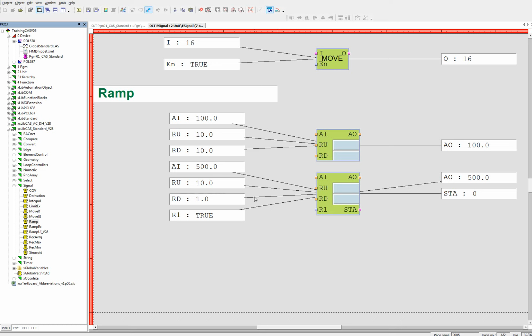This can be really useful, for example, for engines when you have to control the maximum speed. We cannot jump from 0 to 100% of the rotation of the motor. Therefore, there is the ramp up limitation and the maximum speed is controlled according to this ramp up, and the same for ramp down. Then the current is not at the start with a high peak, and it's a really nice rising up of the motor.